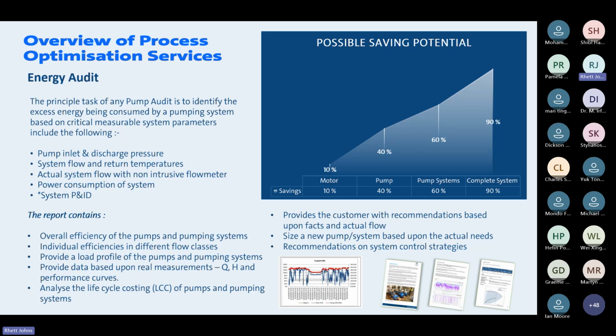Many companies nowadays offer a basic pump check that will review your asset list, take the nameplate off of the pump, and suggest an equal pump with maybe an IE5 motor attached to it. So the issue with this approach is that you're only really achieving that 10% basic motor efficiency improvement that's available through an IE5 motor, and your return on investment is going to be incredibly low. Whenever we want to invest in upgrades in our pumps, we want to ensure that we're getting the best possible energy savings, because at the end of the day, energy is money within a factory, and if we can reduce energy, we can save the factory money.